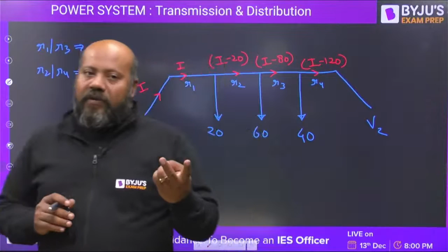First, we have to find R1, R2, R3, R4. Whenever you are dealing with questions related to the distribution system, always remember you should deal with the loop resistance. If it is mentioned in the question, then it is okay. It is not mentioned. He is simply giving you the resistance. So you have to find the loop resistance. What is going to be the loop resistance? Loop resistance is 2 times the resistance, that is 0.15 ohms for 300 meters. Can you tell me what is going to be R1 and R3? It is 0.3 per 300 meters, so 0.3 divided by 300 into 50. What is R2 and R4?